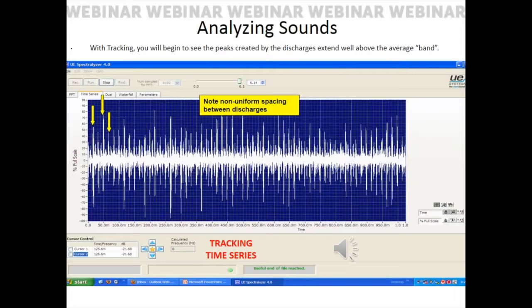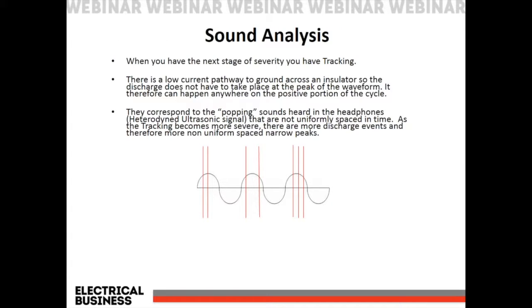And that flashover is going to create uneven spacing because, as we see on the next slide here, the flashover can go wherever it wants to on the positive part of the sine wave, and that's what gives us our uneven spacing, noted by the red lines that are on the sine wave here.